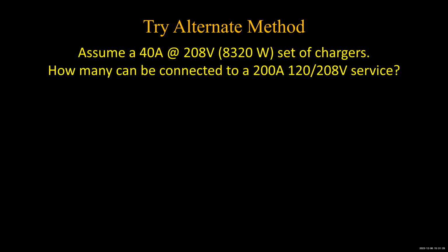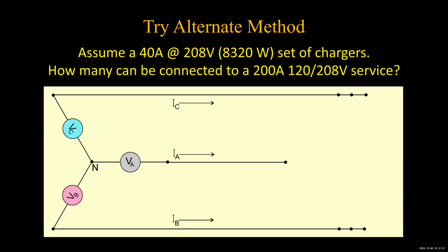208 volt chargers. Let's start connecting some up and see what we get. And then let's connect them and see what the current is. Here's the first one: a 40 amp charger gives you 40 amps, and it's between A and C. So we can argue that A and C both have 40 amps, and we're not paying attention to phase. Obviously they can't both come out, one has to go in, but we're talking AC. The point is the line currents, if you just measure with a clamp-on ammeter, are both going to read 40 amps. All right.